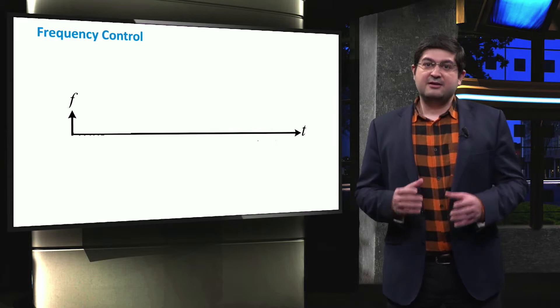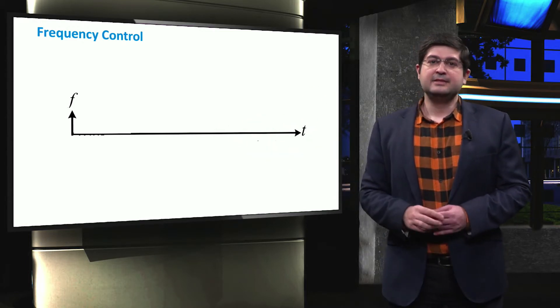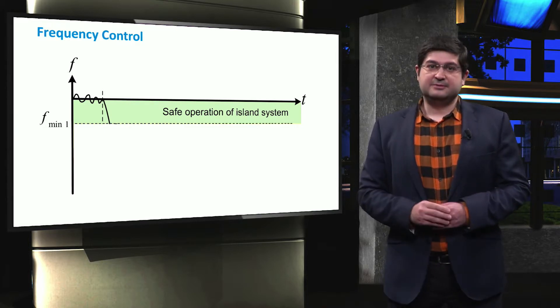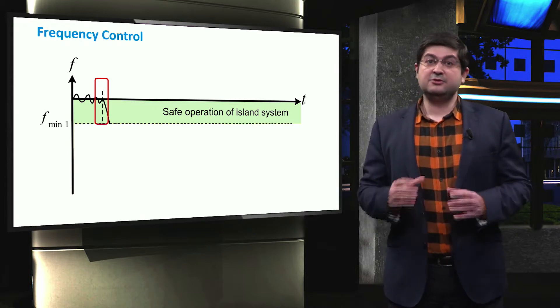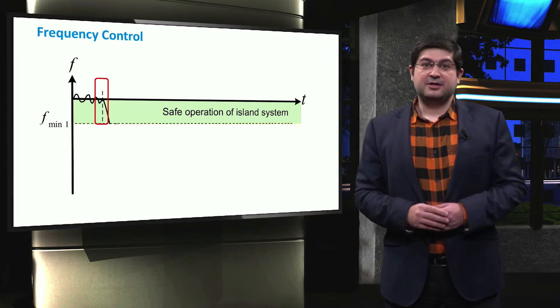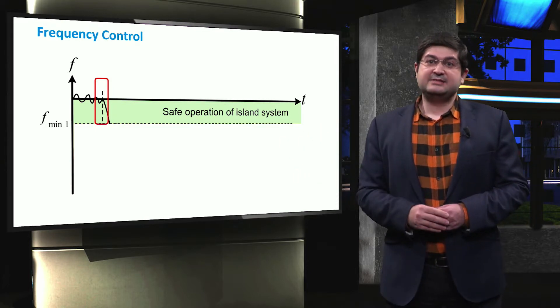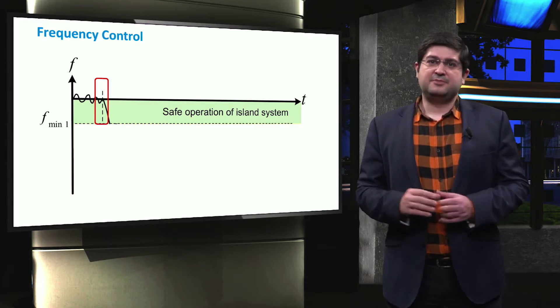In the next slides, we will analyze the frequency response shown on the y-axis over time shown on the x-axis. For the under-frequency event, at the beginning the frequency is controlled almost around the nominal value in the islanded microgrid. However, some moments later, a number of generating units are disconnected, due to which the frequency starts to decrease. The rate of change of frequency in the islanded microgrid depends on the amount of inertia, as well as the implementation of inertia emulation loops. If the frequency can be maintained within the limits, then the islanded microgrid will be under safe operation, where no additional control action is needed.